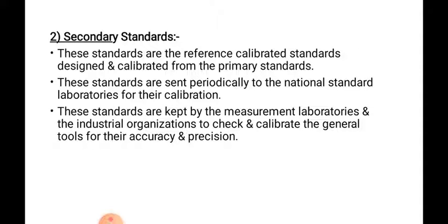These standards are sent periodically to the national standard laboratories for their calibration. I have already told you that on an annual basis there must be a calibration certificate possessed for each and every instrument used at the different shops. Likewise, secondary standards are also sent periodically to the national standard laboratories for their calibration.